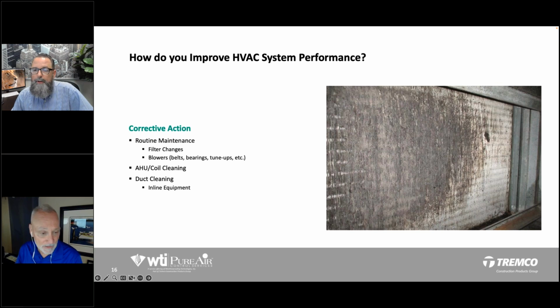Oh yeah. The EPA has done independent studies you can look up, and basically what they're showing is about 3/16 of an inch of fouling, maybe the width of a business card or a little bit more, is going to drop efficiency by 21%.